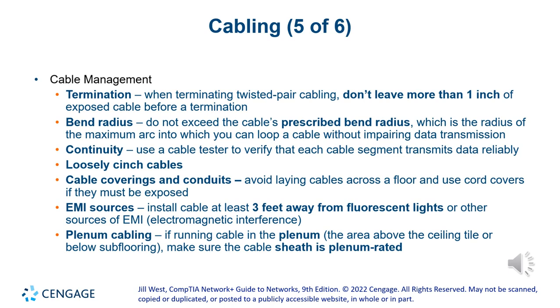Plenum is really important. Remember, plenum I said was the space between the ceiling tile and the floor above. If you're running any cable there, it has to be what's called plenum rated, meaning the sheath is plenum rated. If that catches on fire, the fumes that the cable plastic produces are not toxic, and it is also fire retardant, so it will take a long time and will not catch fire easily.